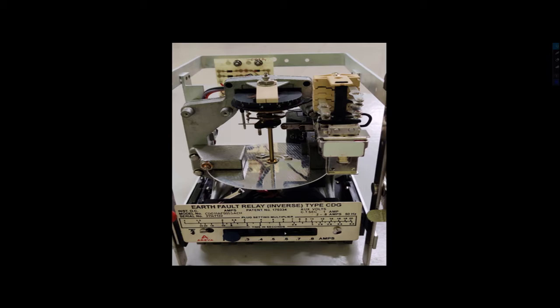In an overcurrent relay, maybe the plug settings are different. Now, this is called the time setting multiplier, and it starts from 0.1 to 1. This is the aluminum disc. That portion is called the relay coil. I will explain the relay coil later. And this is the cover of the relay, and this is one solenoid relay which generates the trip signal.